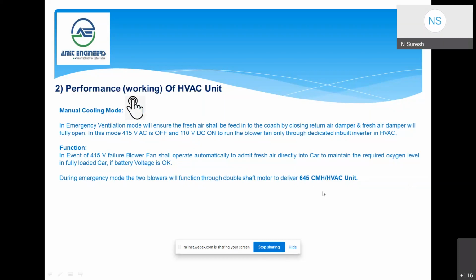There is a manual cooling mode in case of failure of the microprocessor controller. There is a manual cooling mode in the switchboard cabinet. So by activating the manual cooling mode, the system will be able to run and give the desired cooling inside the coach.